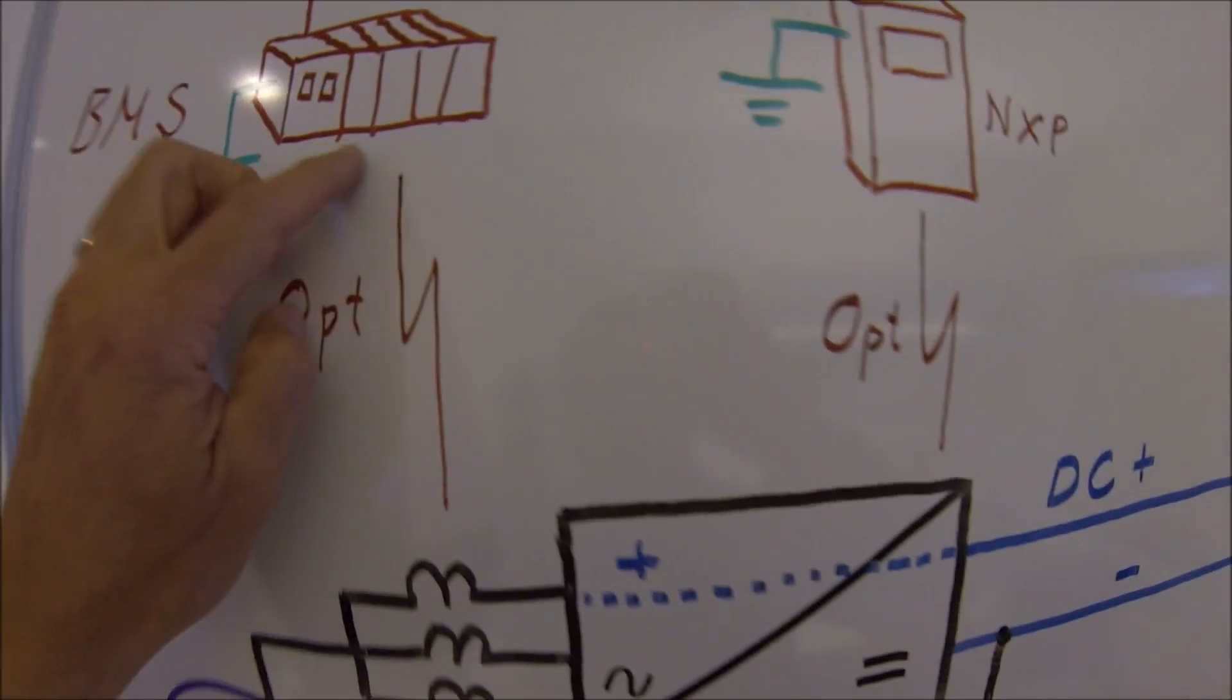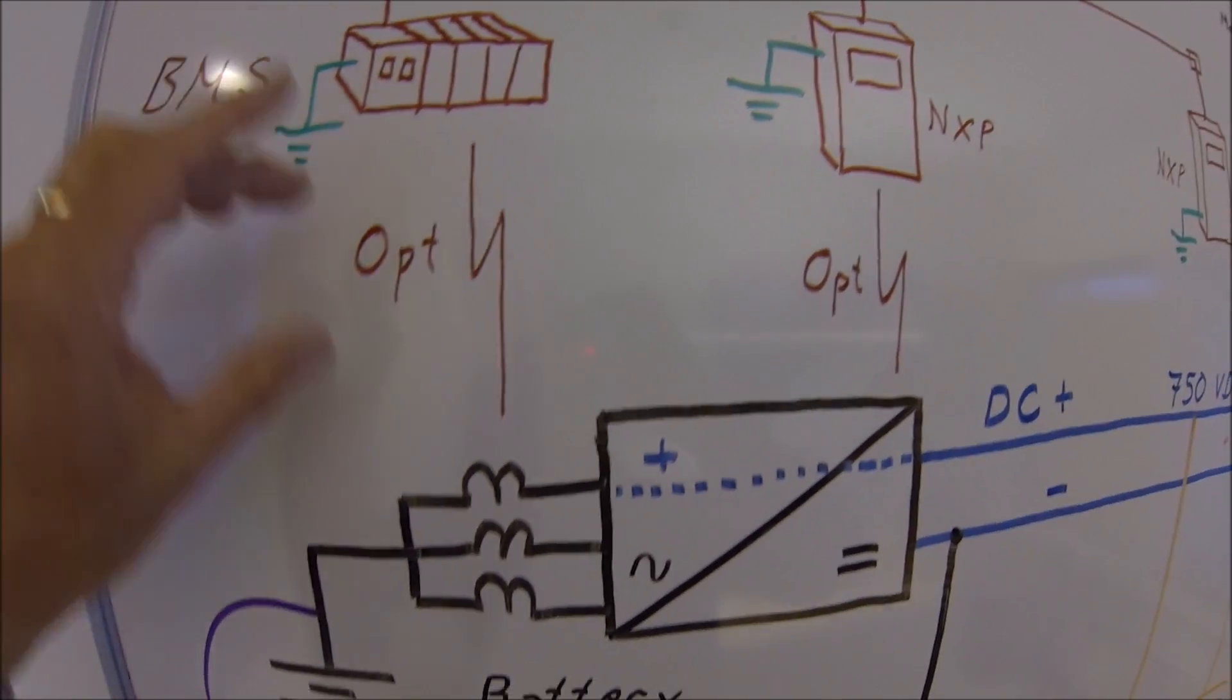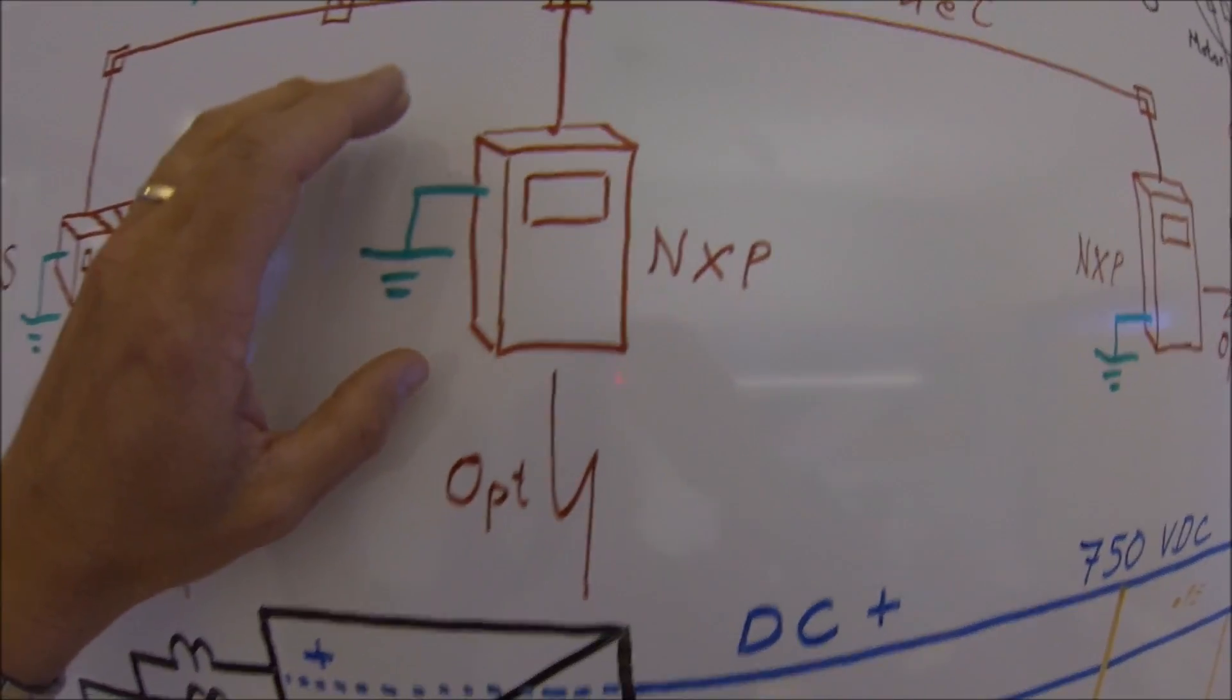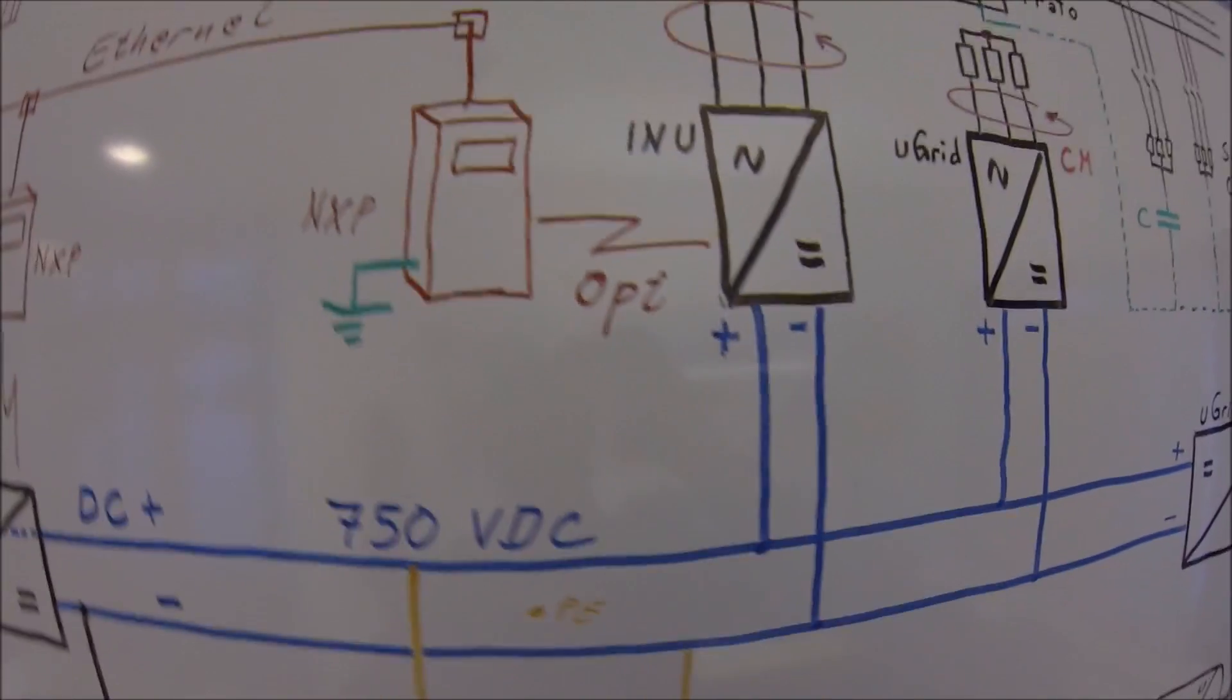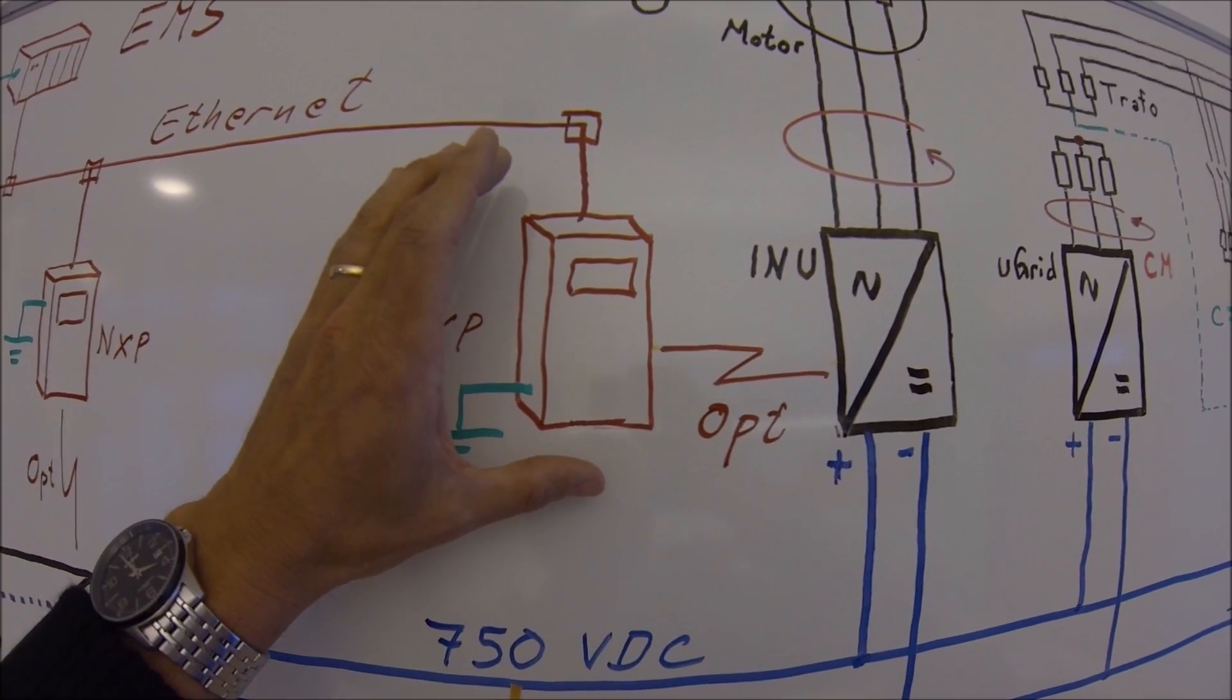You want an optical isolation between these control systems and the battery. Between the NXP control modules and the drives, it is optical fibers. So in this way, you actually don't have a galvanic connection between the control system for the drives and the power modules for the drives.